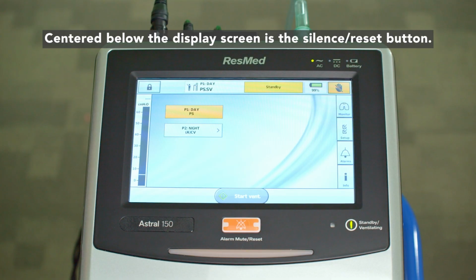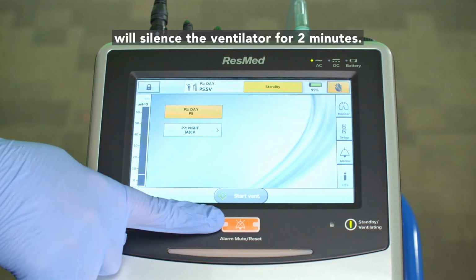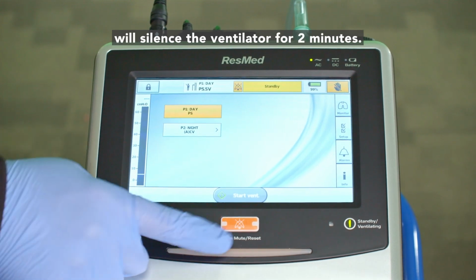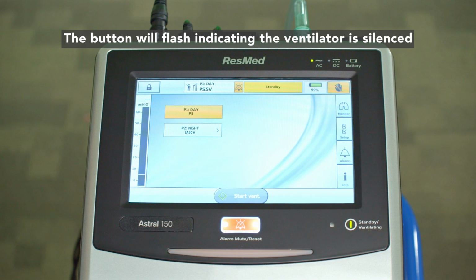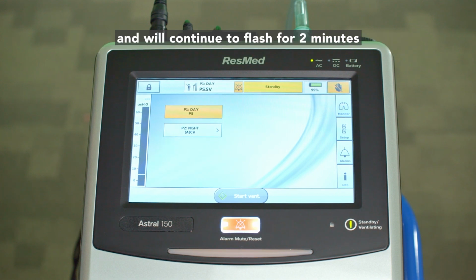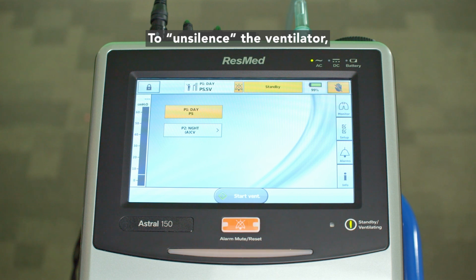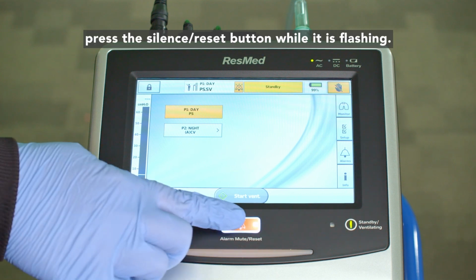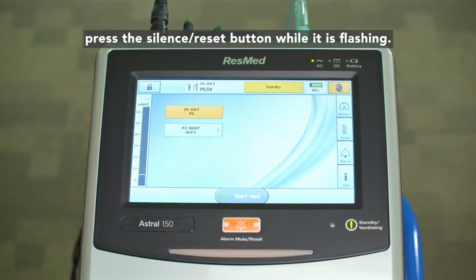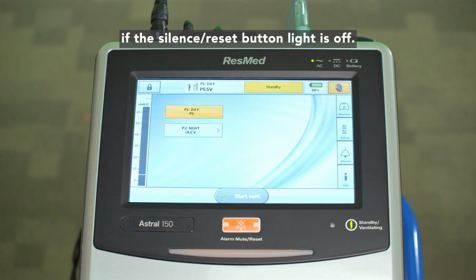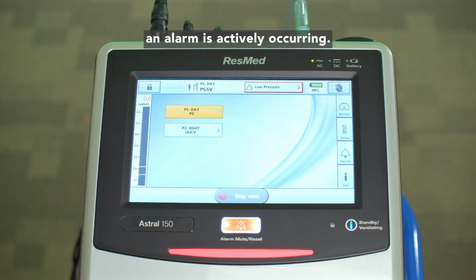Centered below the display screen is the silence reset button. Pressing the silence reset button will silence the ventilator for 2 minutes. The button will flash, indicating the ventilator is silenced, and will continue to flash for 2 minutes or until the ventilator is unsilenced. To unsilence the ventilator, press the silence reset button while it is flashing. The Astral is no longer silenced if the silence reset button light is off. If the silence reset button has a steady light, an alarm is actively occurring.